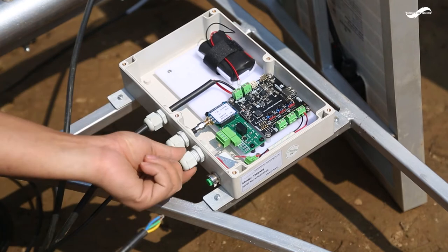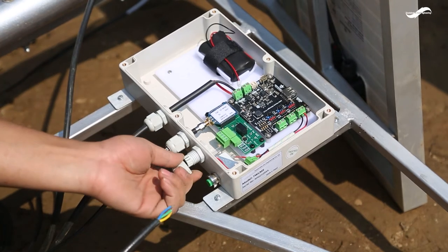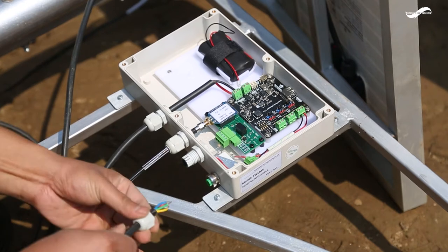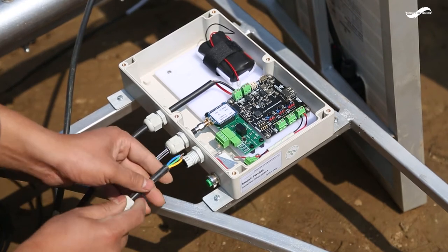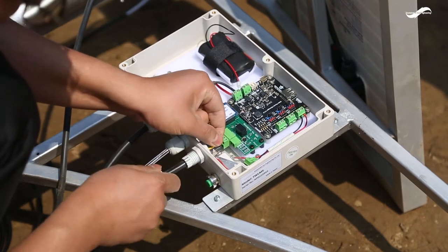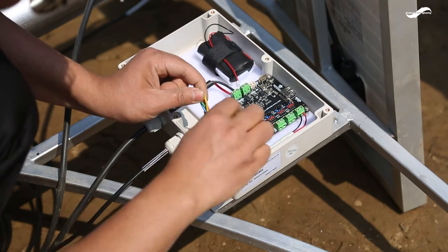Insert the sensor cable through the gland at the right and connect it to the sensor port on the PCB. Ensure the sequence of the cable as blue, red, green, and yellow from left to right.